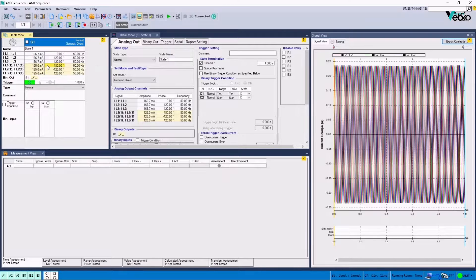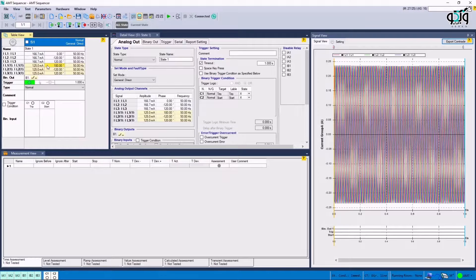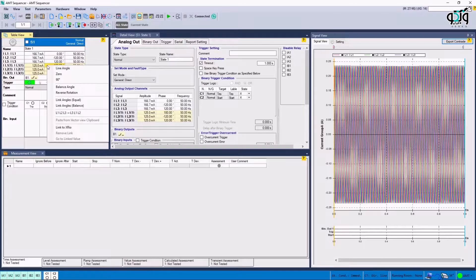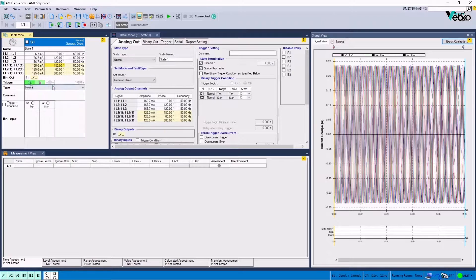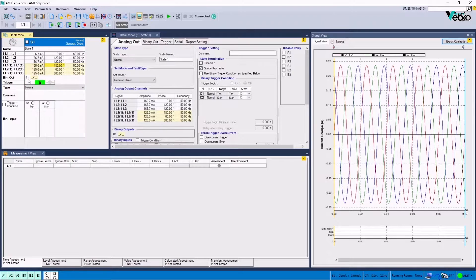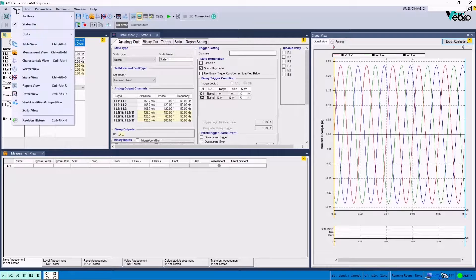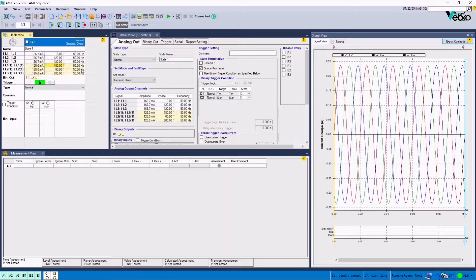Now, since during a stability test, the currents on both sides need to be equal in accordance with the CT turns ratio and have a 180 degree difference. The currents from one side are taken as the bias and a 180 degree difference is considered for currents from the other side. To do so, the current angle of one of the cells is entered and balance angle option is used to apply the angle difference for the other phases. It is possible to view the amount and direction of the current values in Vector View window.